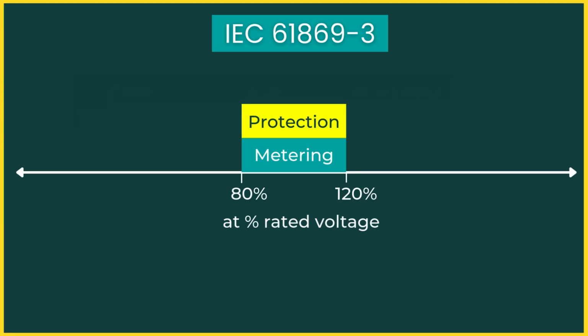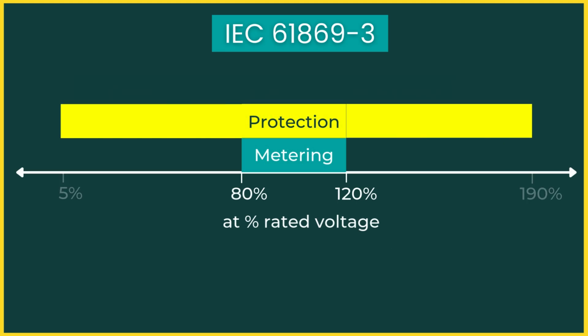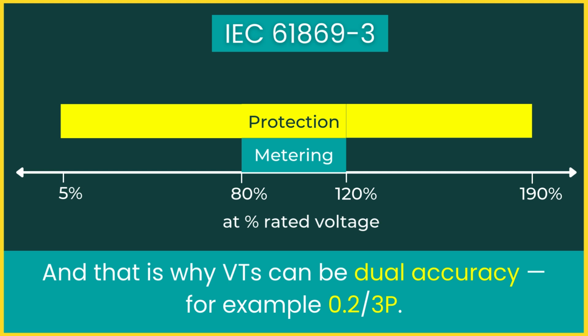Here's the key insight: the two accuracy requirements do not contradict each other. Protection class does not conflict with metering class, it extends the voltage accuracy band. And that is why VTs can be dual accuracy, for example 0.2 and 3P, which means metering accuracy is fulfilled for 80 to 120% of rated voltage. And additionally, protection accuracy and transient response are fulfilled between 5 to 80% and 120 to 190% of rated voltage.